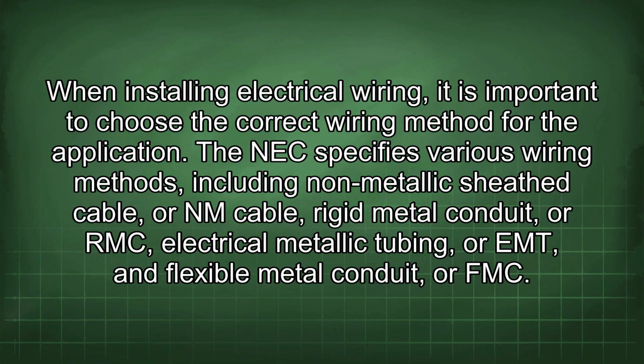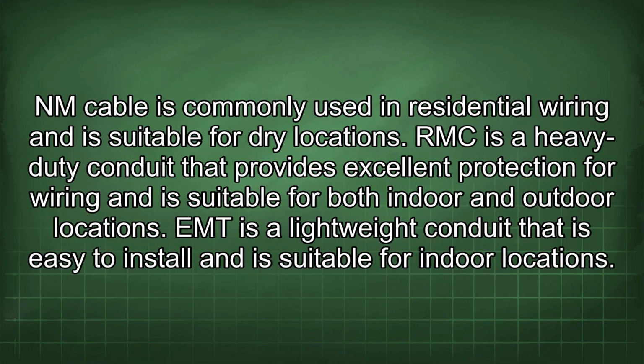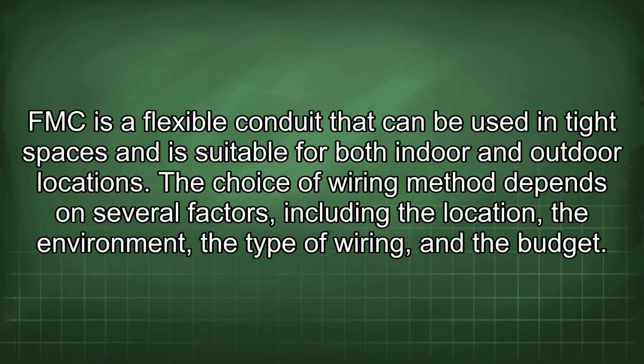When installing electrical wiring, it is important to choose the correct wiring method for the application. The NEC specifies various wiring methods, including non-metallic sheathed cable or NM cable, rigid metal conduit or RMC, electrical metallic tubing or EMT, and flexible metal conduit or FMC. NM cable is commonly used in residential wiring and is suitable for dry locations. RMC is a heavy-duty conduit that provides excellent protection for wiring and is suitable for both indoor and outdoor locations. EMT is a lightweight conduit that is easy to install and is suitable for indoor locations. FMC is a flexible conduit that can be used in tight spaces and is suitable for both indoor and outdoor locations.